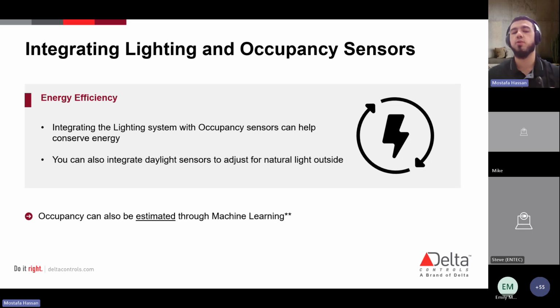One note here, and this is kind of a segue into the artificial intelligence presentation, which is going to happen later, I think around 3 o'clock. Occupancy can also be estimated through machine learning. I'm not throwing that word around because it's a buzzword recently, or because we have a stock that we want to raise the price of. But yes, occupancy can be estimated through machine learning using a combination of parameters like temperature, humidity, things like that. A lot of that goes into algorithms, and again, estimated is underlined, because it's not calculated. I don't want to say exact occupancy can be counted, but it can be estimated through certain thresholds.